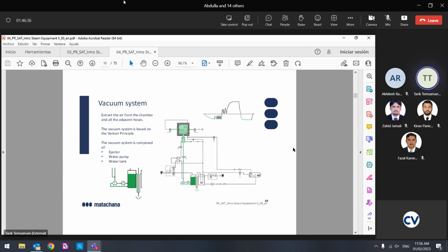It's important to do a vacuum test. If we have a problem, we cannot reach the pressure during the cycle. Of course, during the cycle you have the chamber with a load, so there are many things. But in the vacuum test, the chamber is empty, and we do our test. During the test, we can see what happened: which pressure we reach, and whether it is stable or not. We can get a mini idea of where the problem comes from.